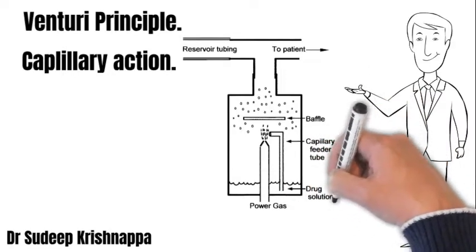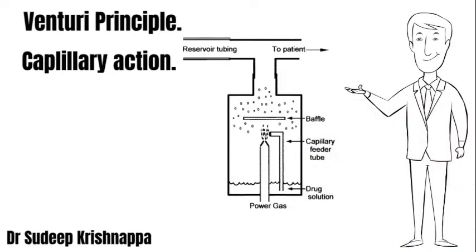We have the oxygen or compressed gas which is led into the chamber by a tubing present at the bottom. At the upper end of this tubing there is an orifice which increases the velocity, thereby producing the Venturi effect. As a result of this, a subatmospheric pressure is generated. Adjacent to this is a capillary tube, the lower end of which is immersed in the solution contained in the chamber and the upper end is closer to the orifice.